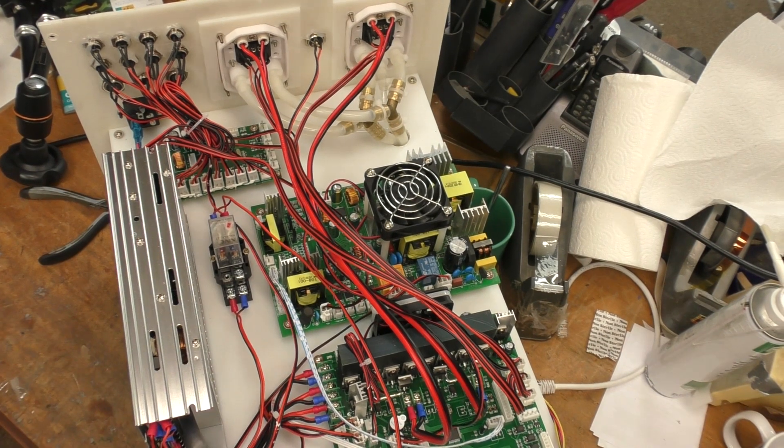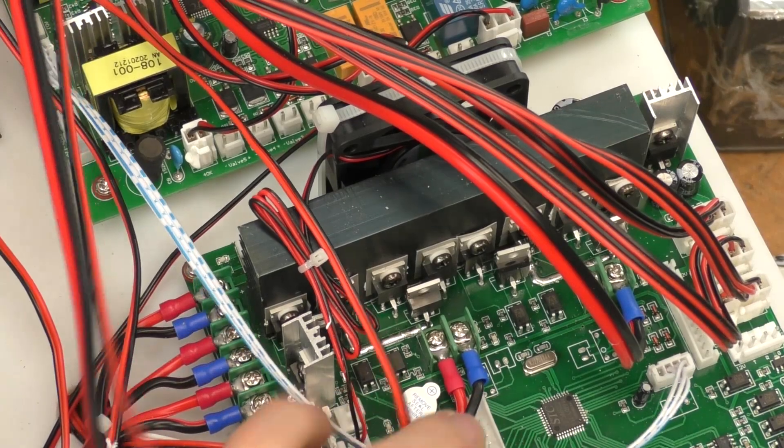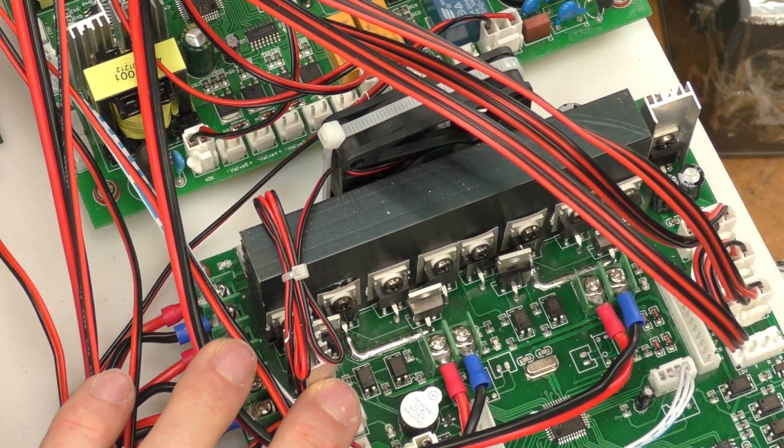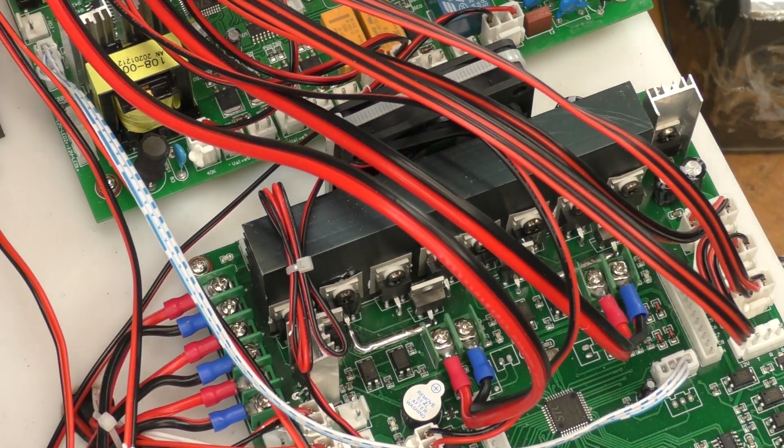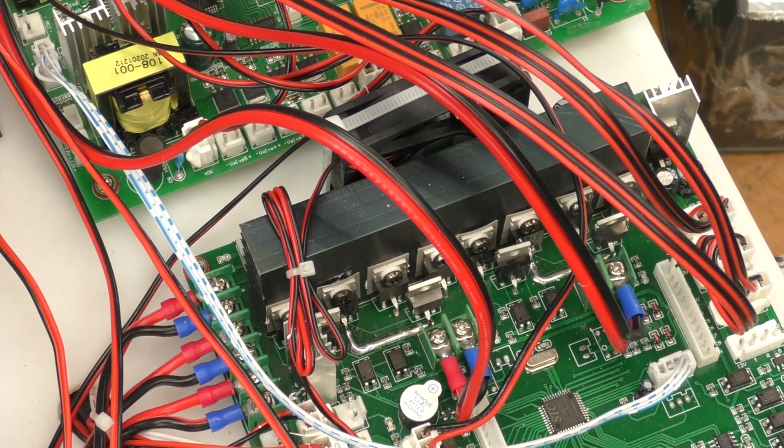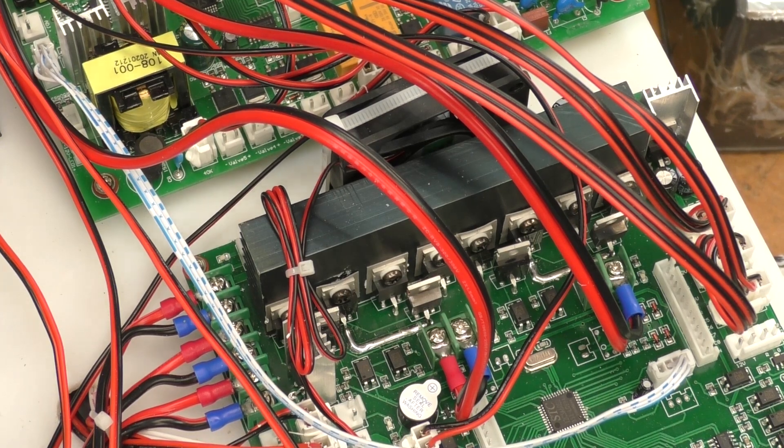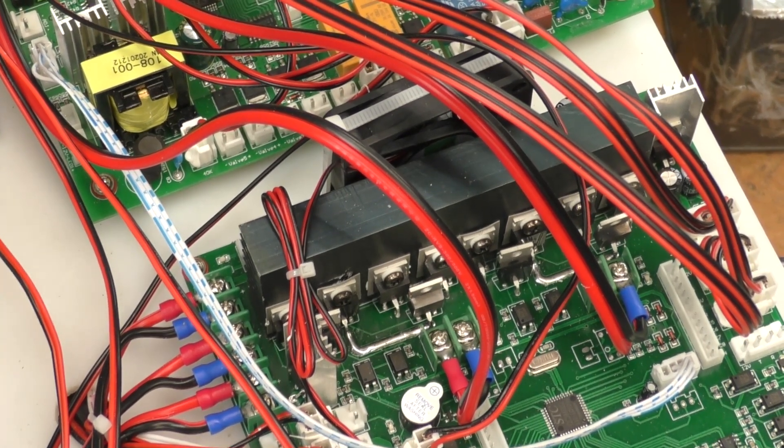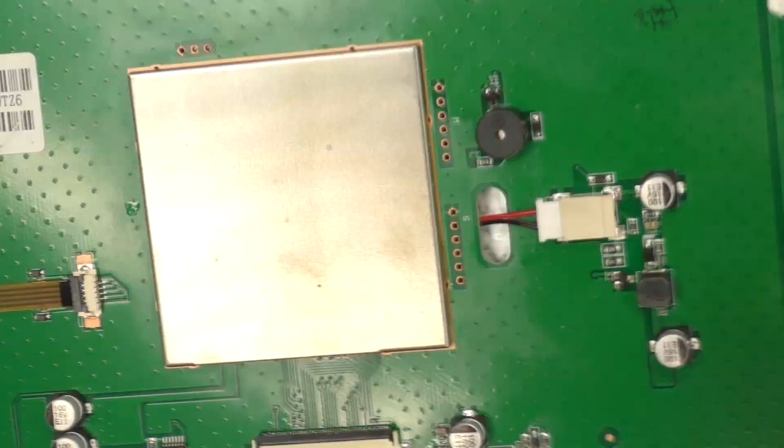This also seems to have some controls for pumps and valves underneath. There's an assortment of control and power stuff, loaded power transistors associated with diode outputs - probably constant current output for the laser diode. There's a communications link to the second board. There's a fairly low-end micro here - an STC 12C5A60S2, which is a very low-end 8051-based micro, clearly only doing very basic simple controls. The LCD display looks like it's got a system-on-chip on the back, so this is a complete user interface module. There's an SD card there, and a fan just cable-tied onto the heatsink.